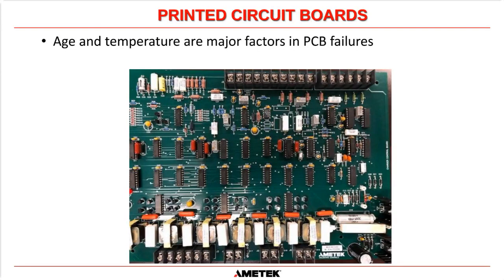Okay. And age and temperature are major factors in PCB failures, in printed circuit board failures. You can see we have a printed circuit board here. Down in this bottom right-hand corner, there's a DC electrolytic capacitor. And also there are some tantalum capacitors on this board here. They look like tantalums, and that actually looks like a tantalum as well. They are all age related, and basically we say they have a 10-year life as well at nominal temperature, which for our systems I think is 100 degrees Fahrenheit. So if the temperature of the system goes above 100 degrees Fahrenheit, then these capacitors will start to age quicker. That's why it's extremely important to keep the airflow of the fans and to replace the printed circuit boards every 10 years. Okay.